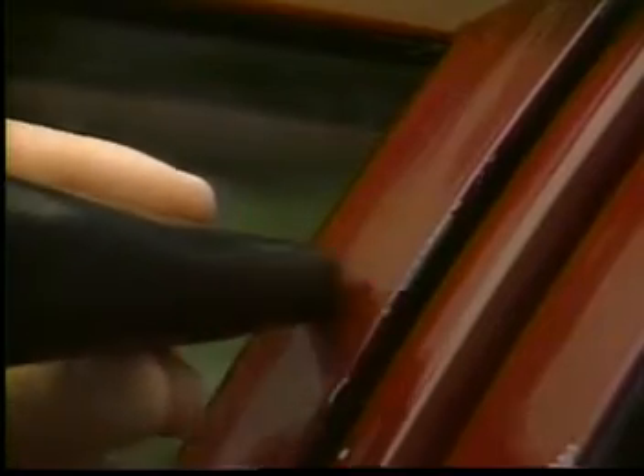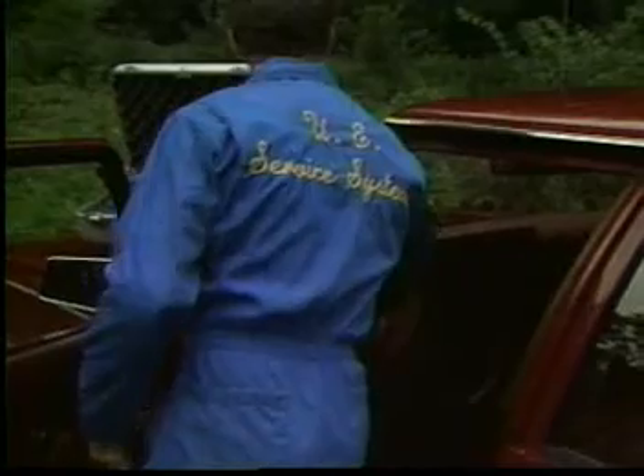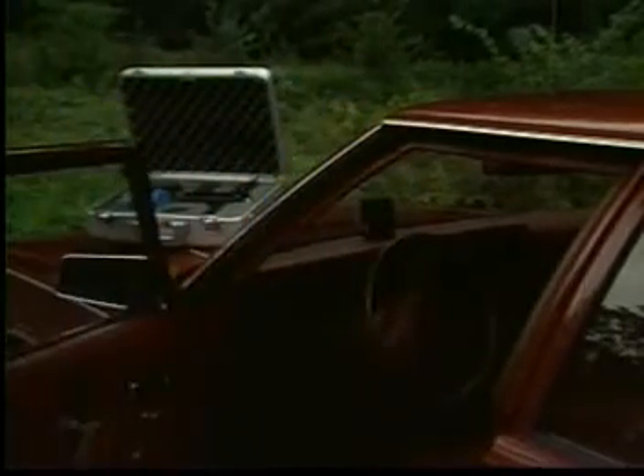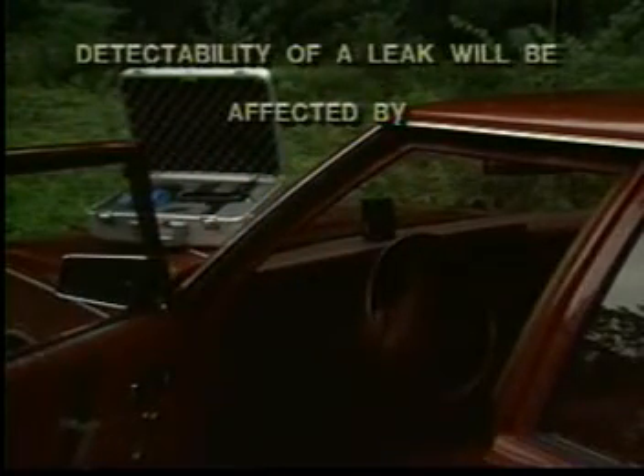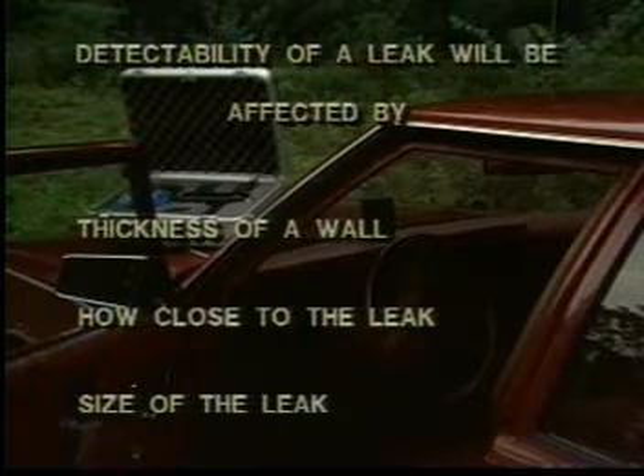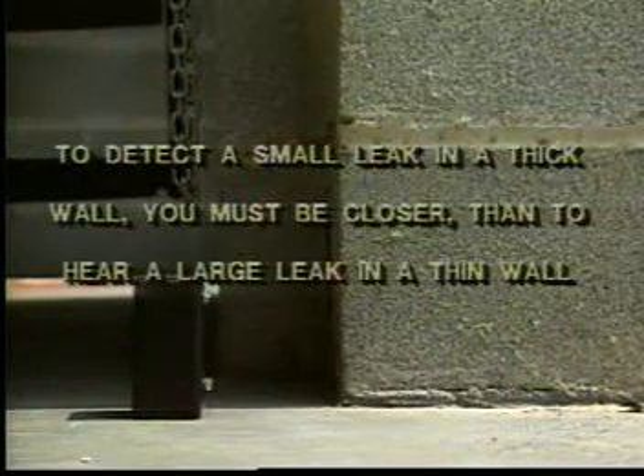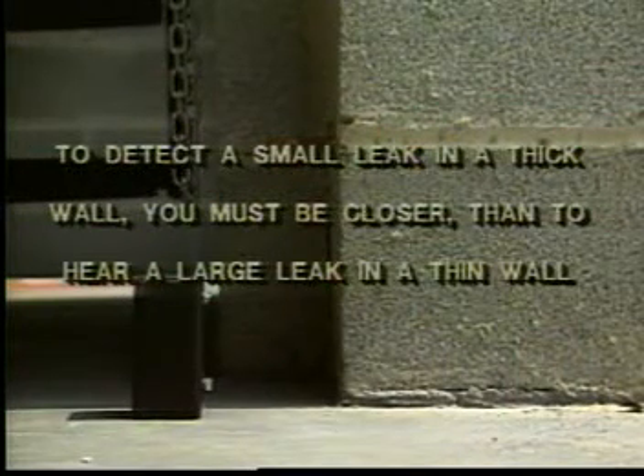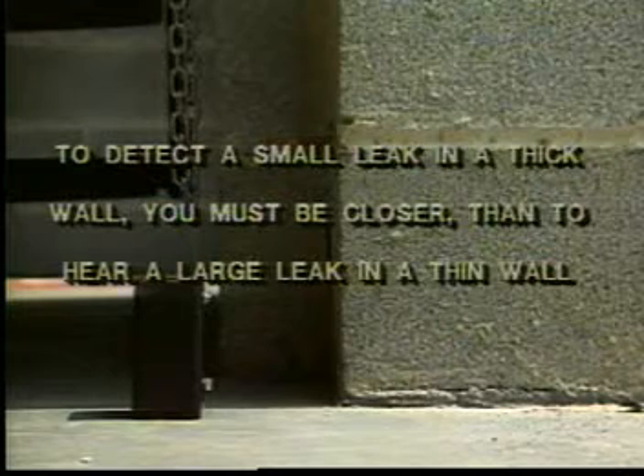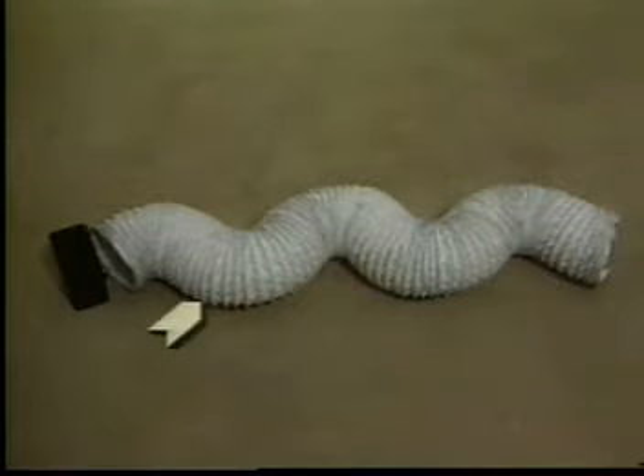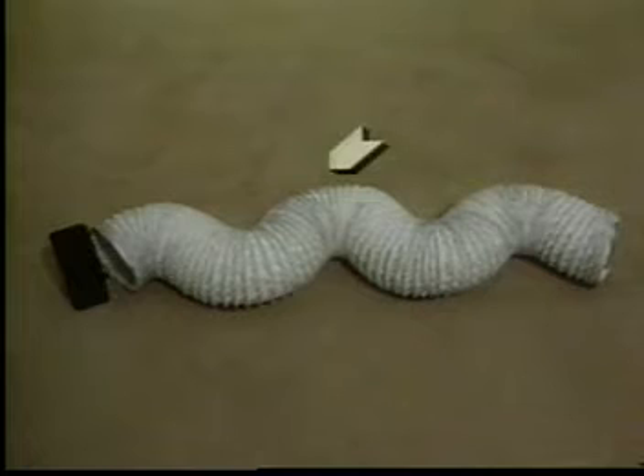Listen to the ultrasound penetrating this seal. When placing the warble tone generator, the following factors should be considered. First, the detectability of the leak will be affected by the thickness of the wall, how close you can be to the leak, and the size of the leak. To detect a small leak in a thick wall, you must be closer than to hear a large leak in a thin wall.